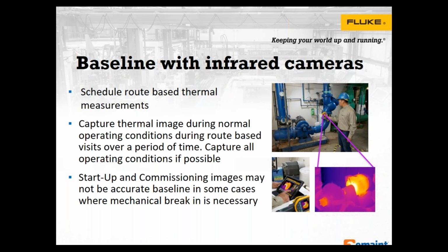Okay, so we talked about some assets where you get a clear set of data output coming from it, and I want to use the final part of this time to discuss a more complex type of asset trend, something that's becoming more and more common in industry: using infrared cameras and how to baseline with infrared thermography. In this particular case, we're looking at a pump motor with the thermal camera.